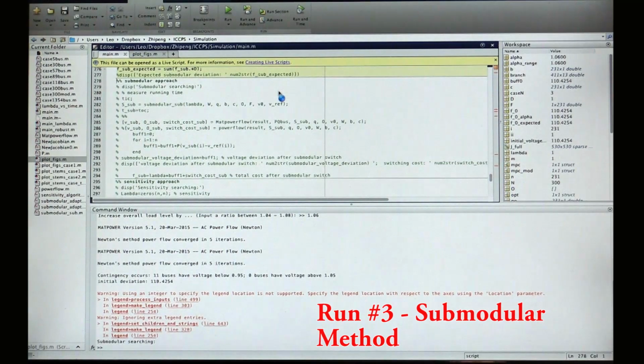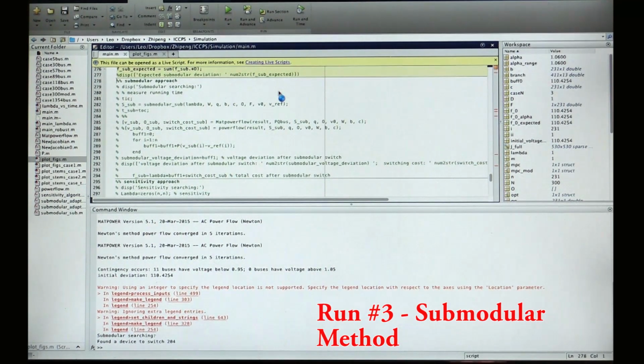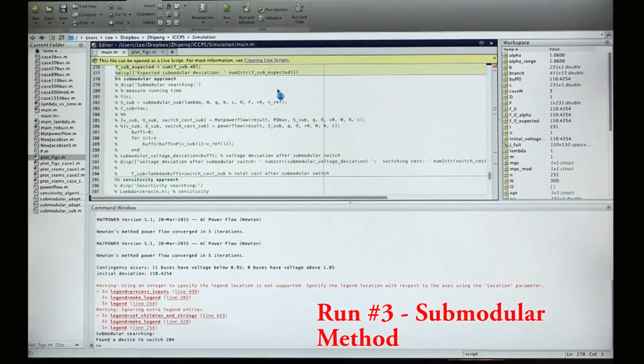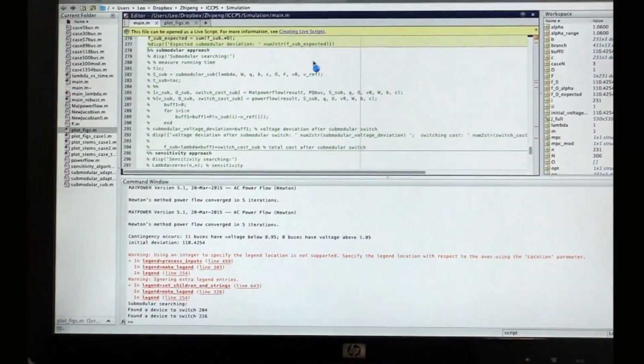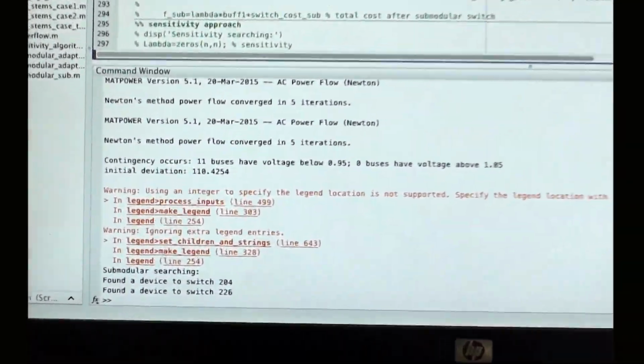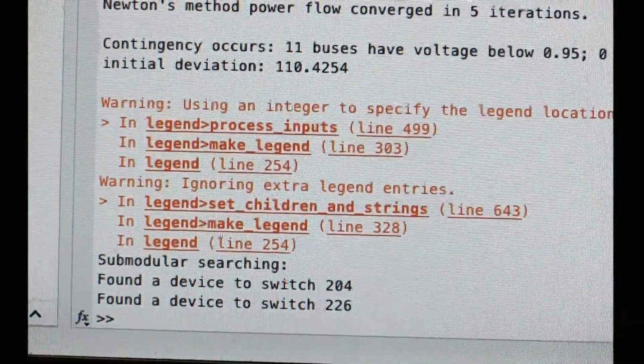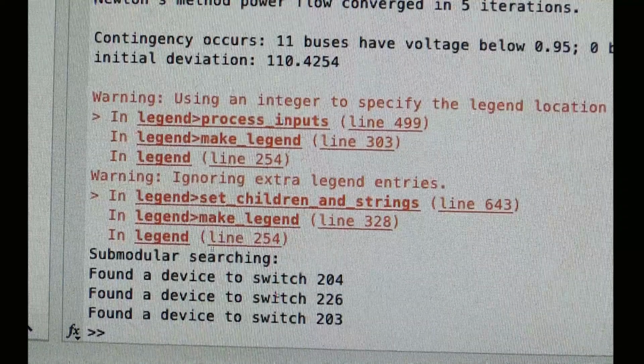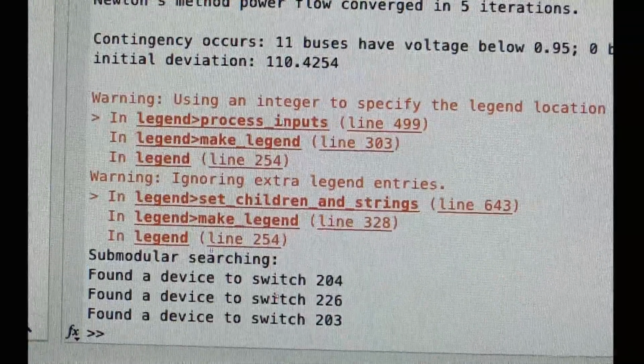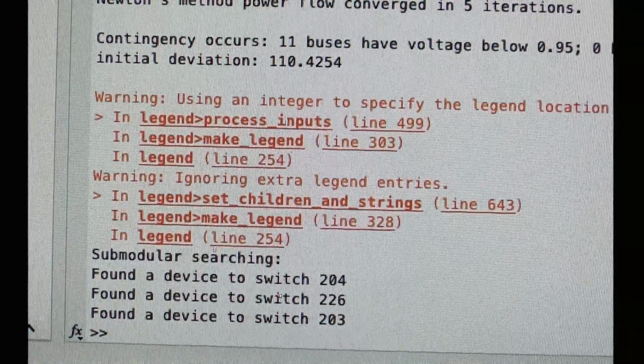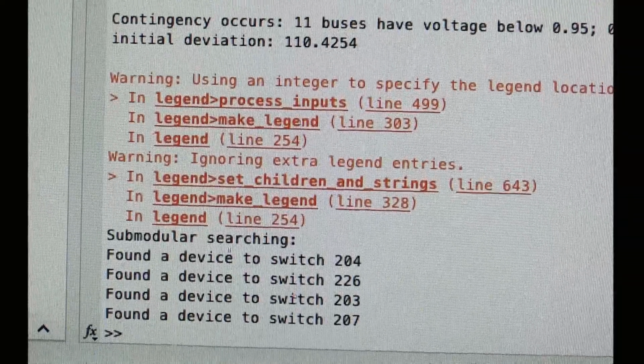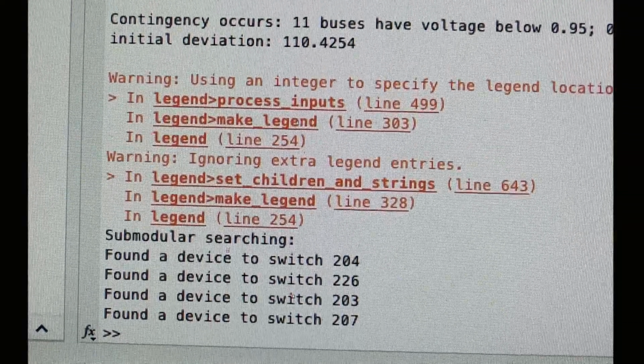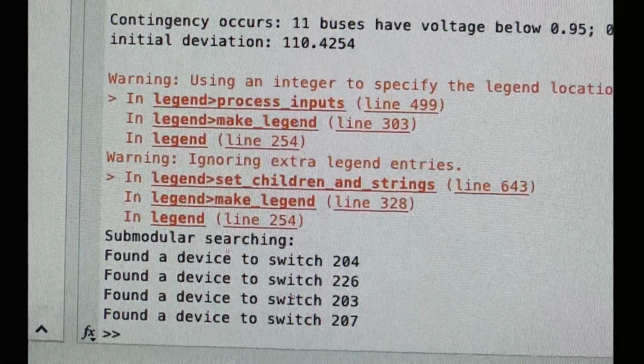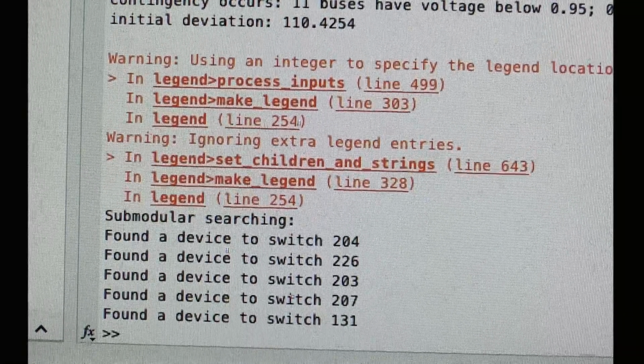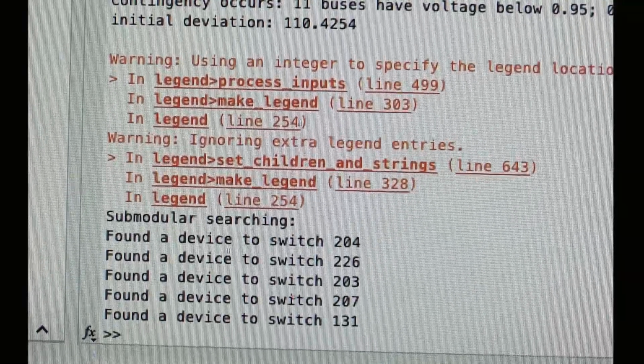Now our submodular method begins to work. It selects which bus to inject reactive power such that the low voltage problem can be fixed. The submodular algorithm works as follows. It first formulates a cost function that captures both the switching cost and the predicted voltage deviation after control. In each iteration, it greedily selects the bus where injecting reactive power can lower the cost the most.